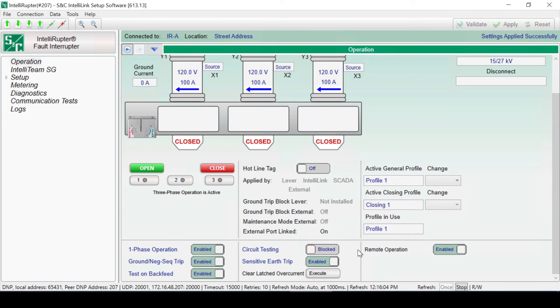The Active Closing Profile will always revert back to Closing Profile 1 after a close operation occurs. The most common application is to set Closing Profile 1 to perform a pulse-close test and set Closing Profile 2 as a point-on-wave profile.